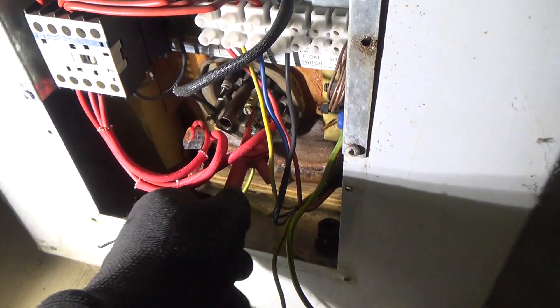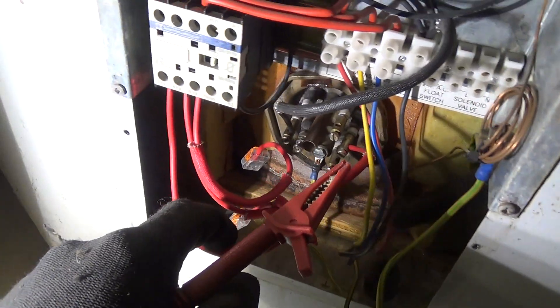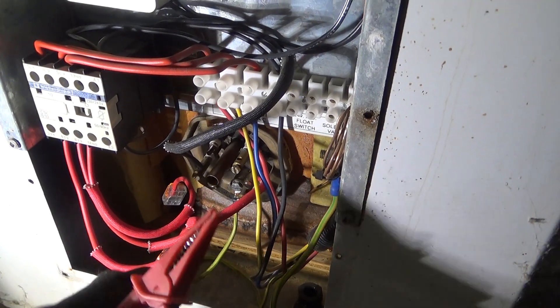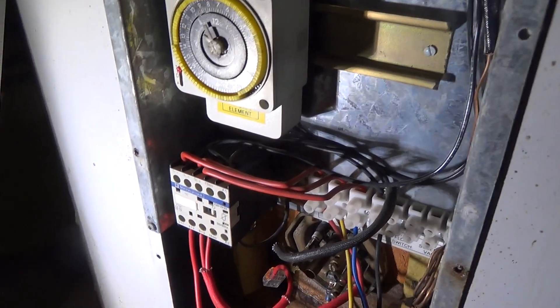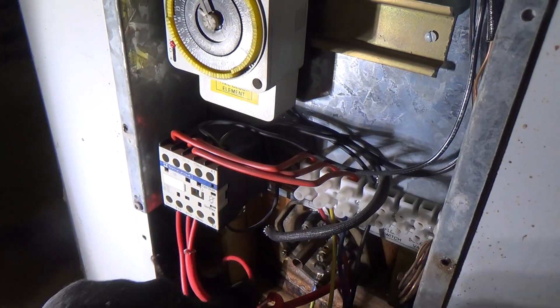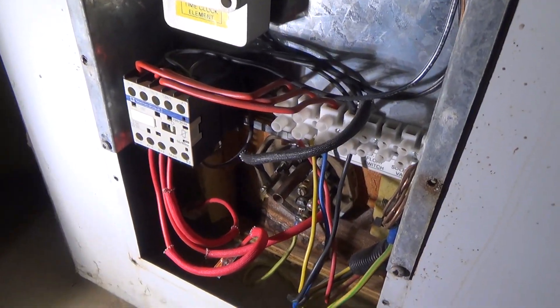Now that has shown a dead short — it is a dead short. Although, could it be going possibly up the neutral? I'm not sure if that switch switches off the neutral, so we might pull the incoming neutral off of there just to be sure.